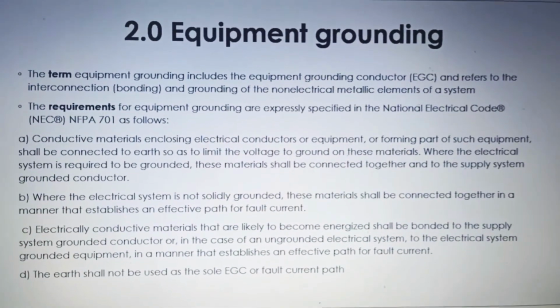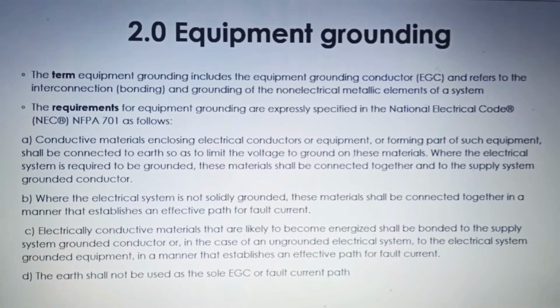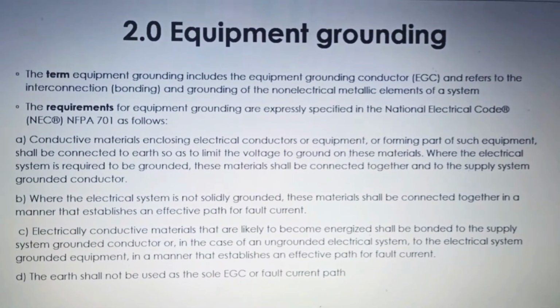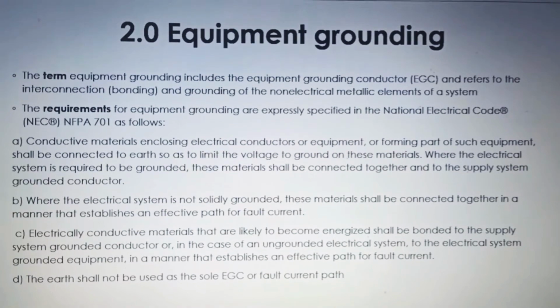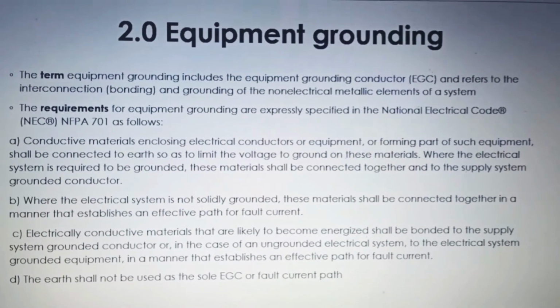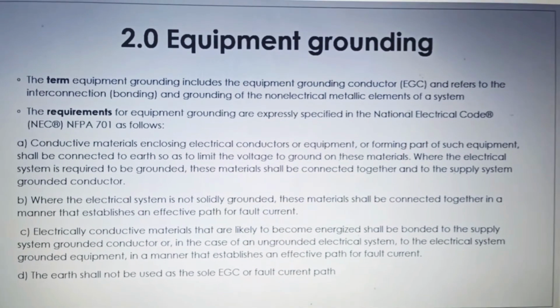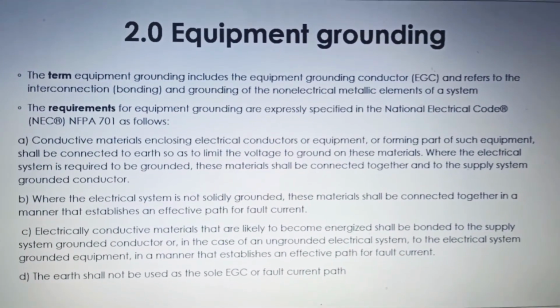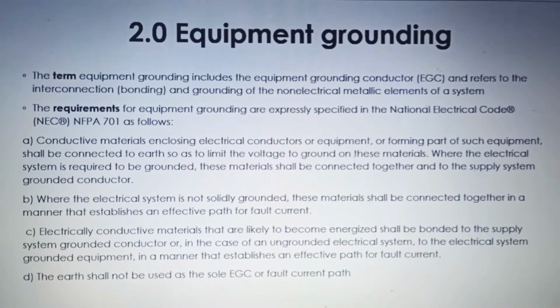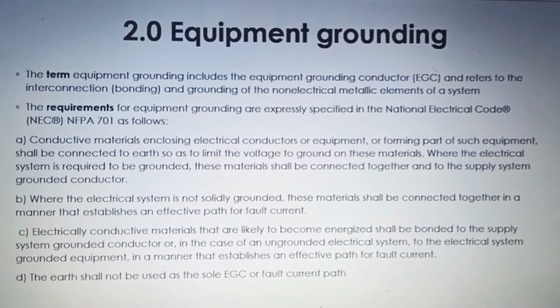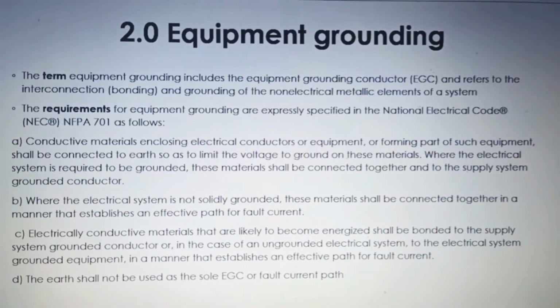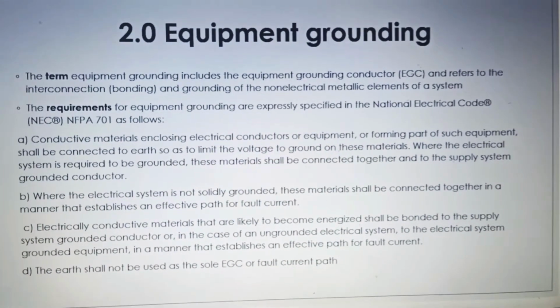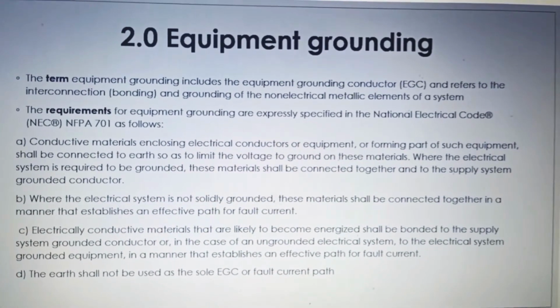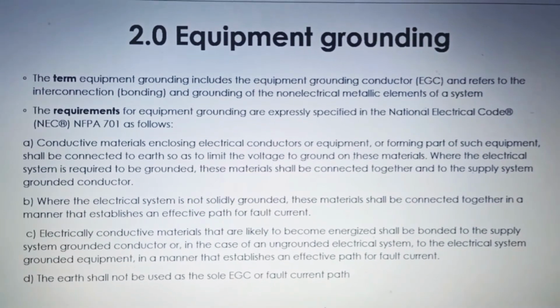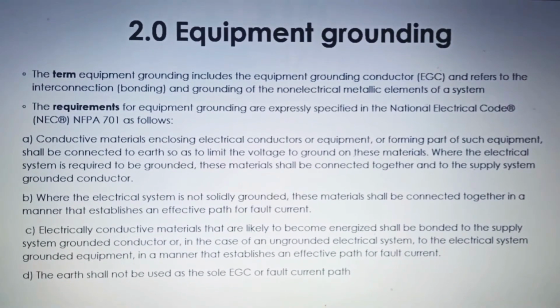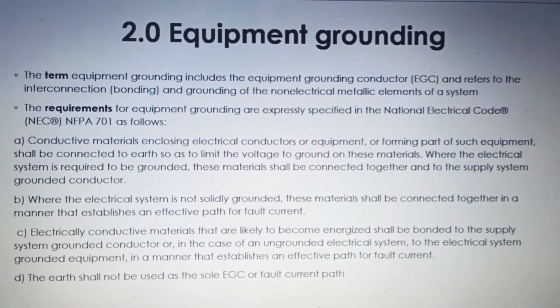The requirements of equipment grounding are expressly specified in the National Electrical Code, which is the NEC, as follows. Conductive material enclosing electrical conductors or equipment shall be connected to earth so as to limit the voltage to ground on this material. Where the electrical system is required to be grounded, this material shall be connected together and to the supply system grounded conductor. Where the electrical system is not solidly grounded, this material shall be connected together in a manner that establishes an effective path for fault current.